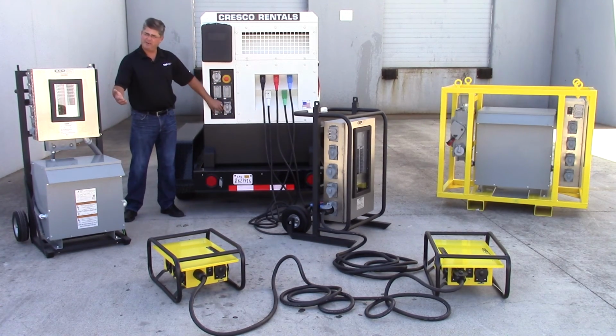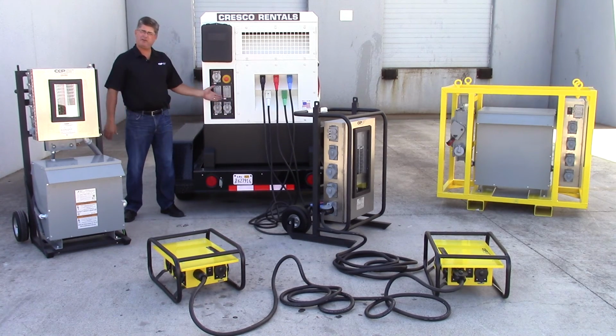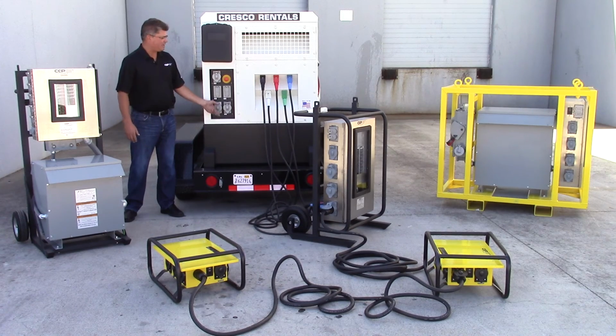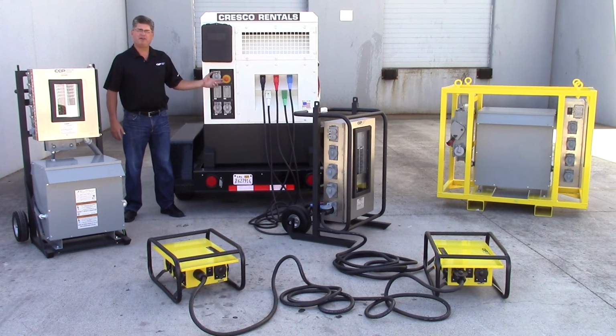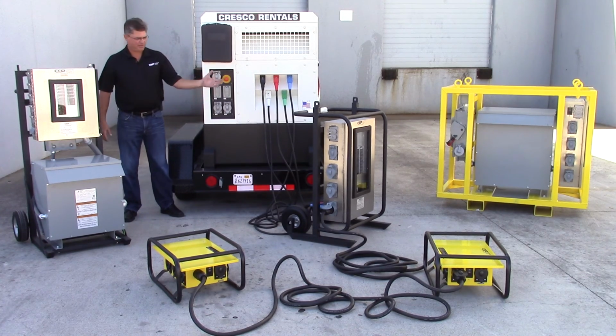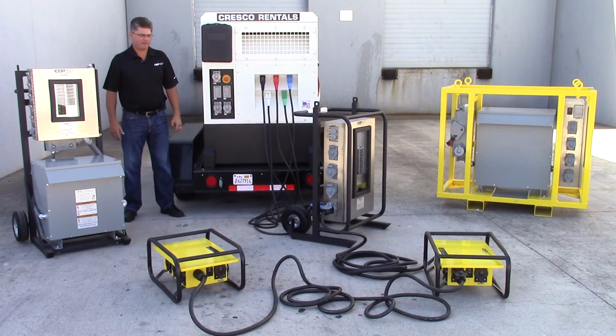smaller unit, the 25 kW, offered. However, when you're utilizing these receptacles, this is single phase power, and it's only pulling power from 2 of 3 windings that are in this generator. So in essence, if you're utilizing these and not utilizing 3-phase power, you're leaving 1/3 of the power in this generator. So that is the main purpose for these 3-phase power distribution units.